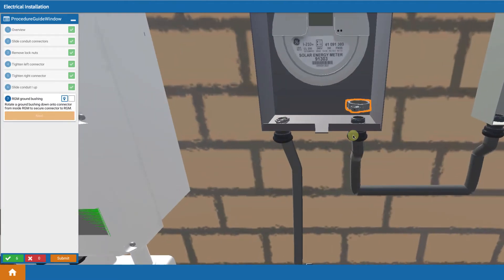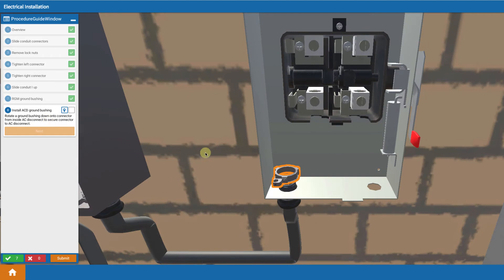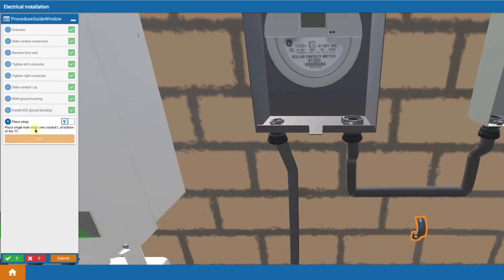And then inside, we're going to seal these things or connect these things with ground bushings, bonding bushings. So you're going to install a bonding bushing down inside the revenue grade meter and another bonding bushing down inside of the AC disconnect.